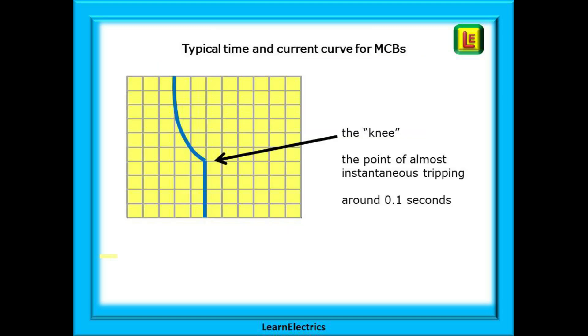This is a typical time and current curve for an MCB, a nice smooth curve for the most part. But they also have what is called a knee, a point at which they will trigger almost instantly which can be as quick as 0.1 seconds or less.